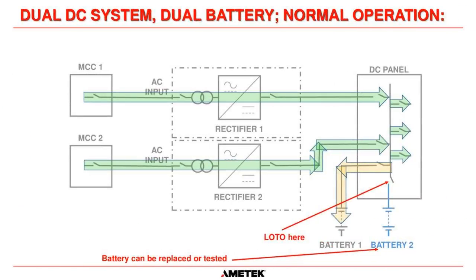And the same can be said for a battery. You can see here that battery 2 has failed. We want to replace it. So charger 1 stays on, charger 2 stays on. All we do is lock out, tag out the battery disconnect going to battery 2, and we can replace that battery, or we can do a capacity test on it. We can do whatever we want.